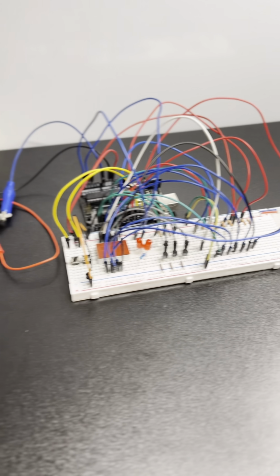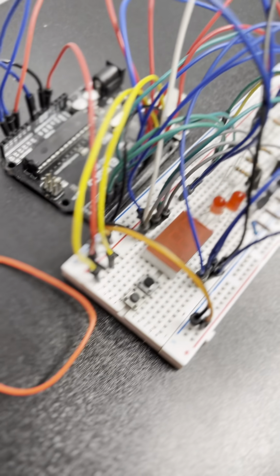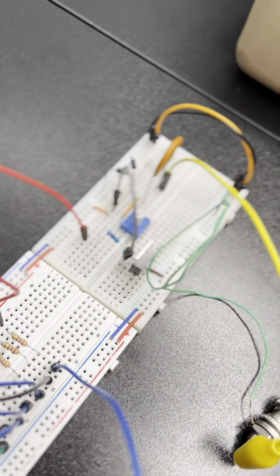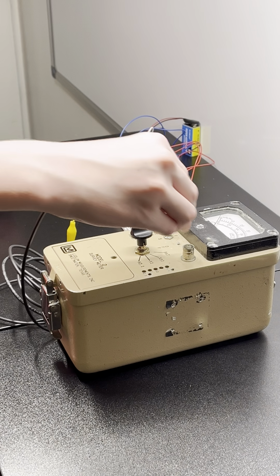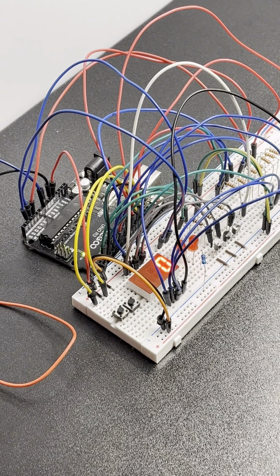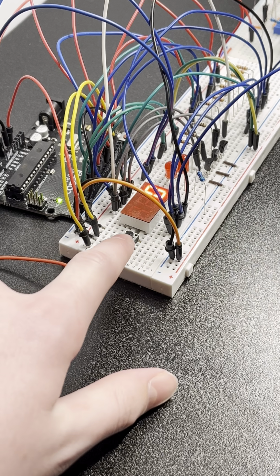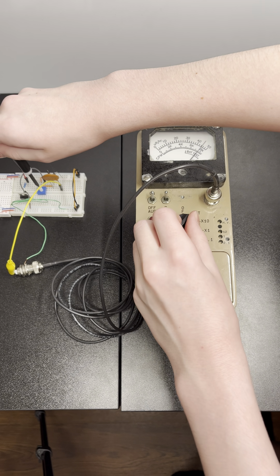A pulse calibration must be performed to ensure the instrument reading aligns with the incoming counts, and I can do this using this pulser that I hand built. I ensure a steady connection with the Model 2 and power both the pulser and the Model 2 on. I enable the pulses and then dial in the amplitude until I get counts on the meter.